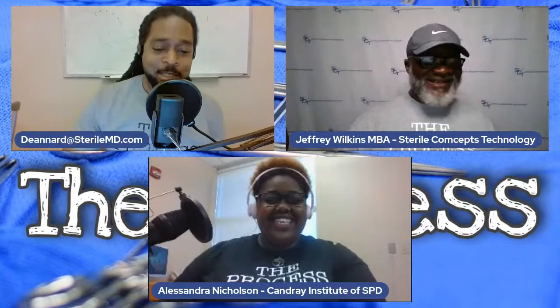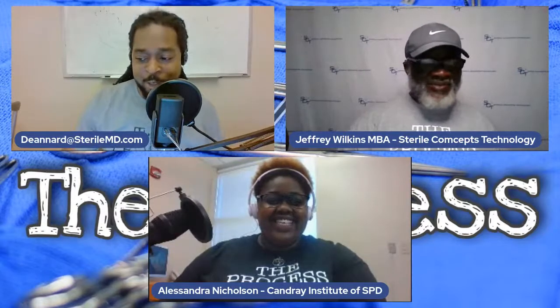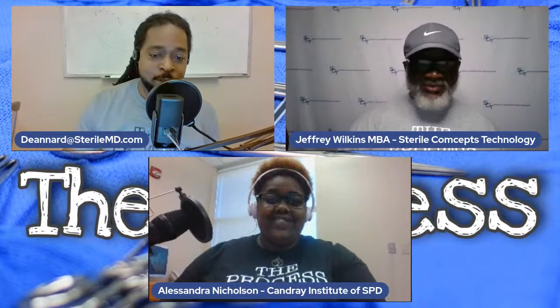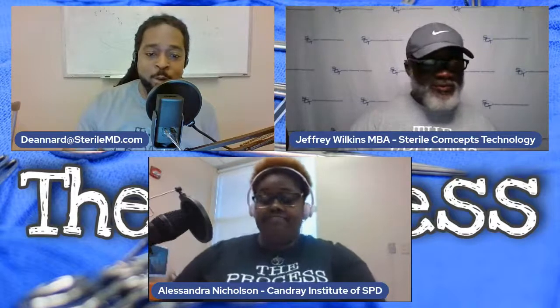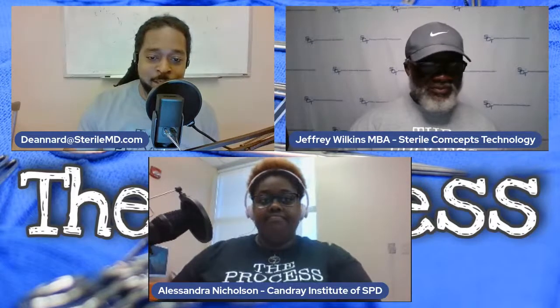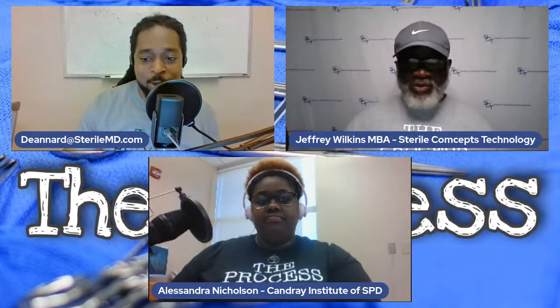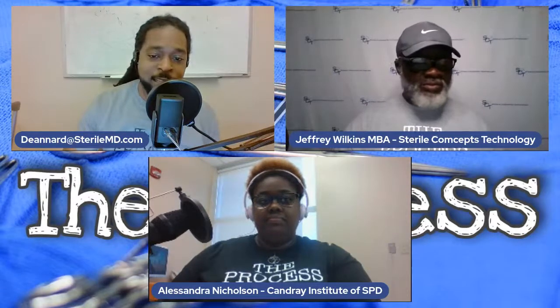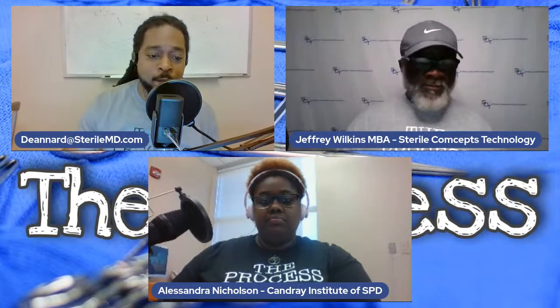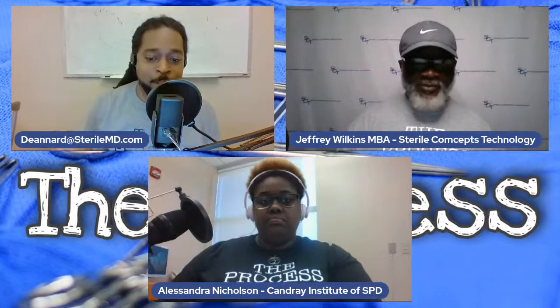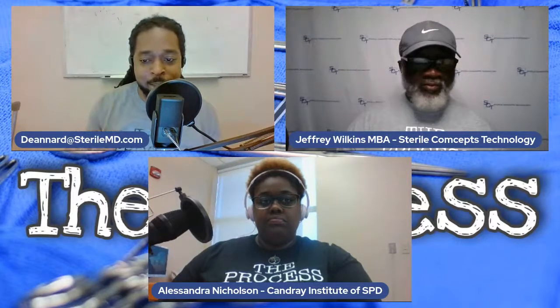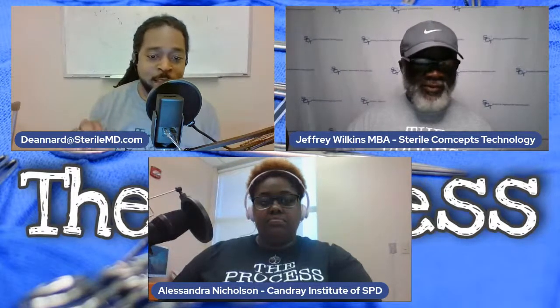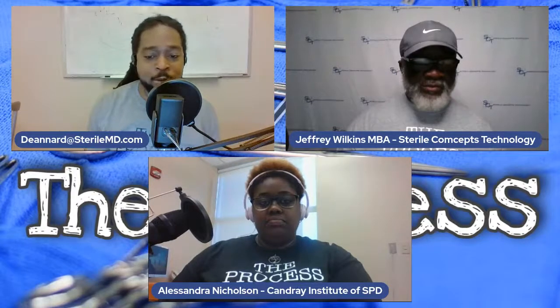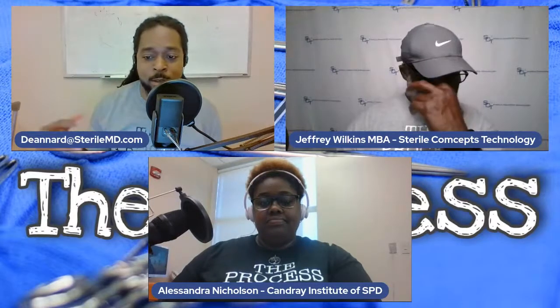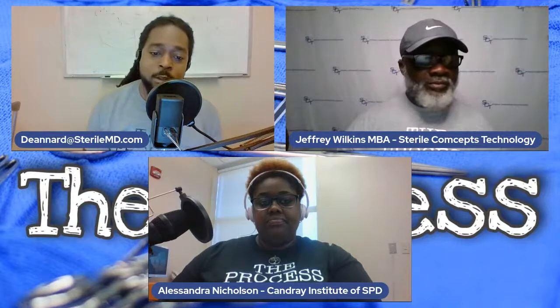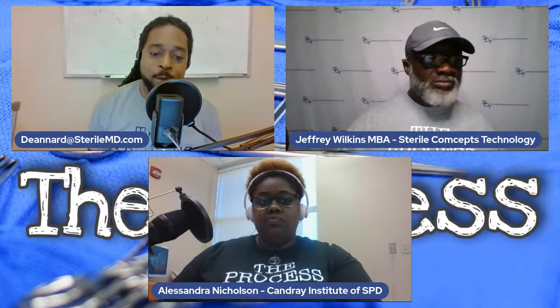So let me just say something. IFU stands for instructions for use, but it definitely doesn't mean that's the only thing you could do, right? I'm not speaking in terms of sterilization. I'm speaking in terms of cleaning and just maintaining your instrumentation. Every IFU won't have every single thing you can do. So then we have to use our better judgment in terms of using lubrication on the clean side, or using a metal brush.